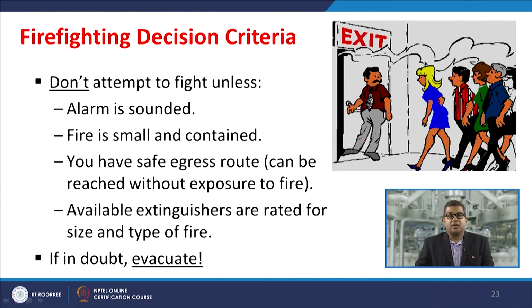Now, don't attempt to fight the fire unless the alarm is sounded, the fire is small and contained, you have a safe egress route that can be reached without exposure to fire, and the available extinguishers are rated for the size and type of the fire. And if you are in any iota of doubt, then you must evacuate along with your co-workers. So you must evacuate the workplace.